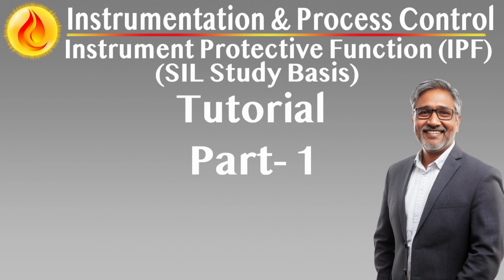Testability, diagnostics, and degraded mode strategy. IPFs must be fully testable within defined intervals, with diagnostic coverage designed to detect latent faults before demand. Systems should support automated diagnostics where feasible and provide degraded mode alerts to operators, including bypass status, test failure, and input loss. Upon detecting a fault, the system must default to a safe state and provide clear alarms. Where necessary, degraded mode strategies, e.g. override conditions, alarm escalation, must be defined and integrated into both the DCS and safety instrumented system.